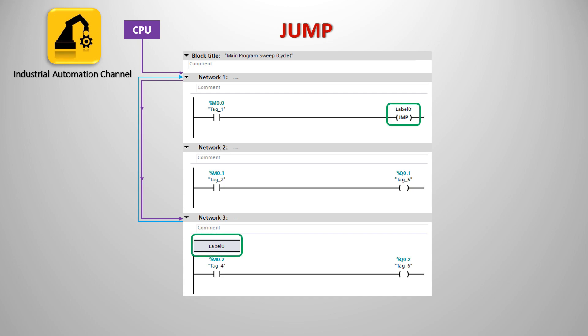It's used to interrupt the execution of a program and resume the scan from another network. The destination network must be identified by a jump label. Here you see we have three networks. As long as M0.0 has a false value, as usual the first network will be executed. Then the second one.